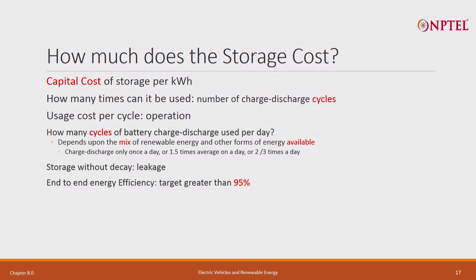End-to-end energy efficiency — what you have to do is take AC energy, convert it to DC, charge, store, take out the energy, convert the DC energy back into AC. What is the end-to-end loss? Typically for large batteries you can get 95, 96, 97 percent — so there is a 4 to 5 percent loss for lithium-ion battery. That is kind of the best you can do, probably 97 percent, and tomorrow it may become 98 percent.